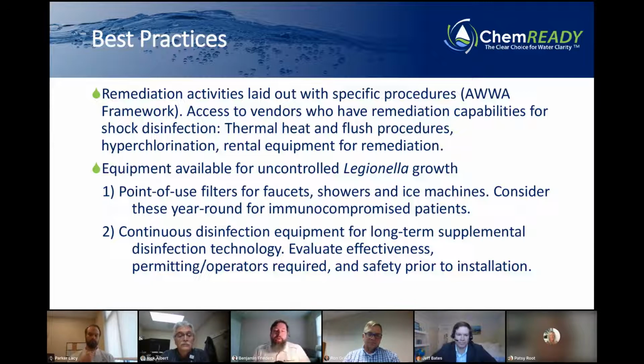Finally, equipment available for uncontrolled Legionella growth. If you find yourself with greater than 30% positivity rate or uncontrolled Legionella growth, have access to the best practice equipment out there. Short-term remediation that protects staff and residents would be point-of-use filters—the CDC requires less than 0.2 micron filters. There are specific Legionella filters for faucets, showers, and ice machines. So if you have a system outbreak and don't have the capability to do a shock disinfection quickly, you could use point-of-use filters as a temporary solution until the larger fix can be done. Again, this means having access to vendors with that capability.